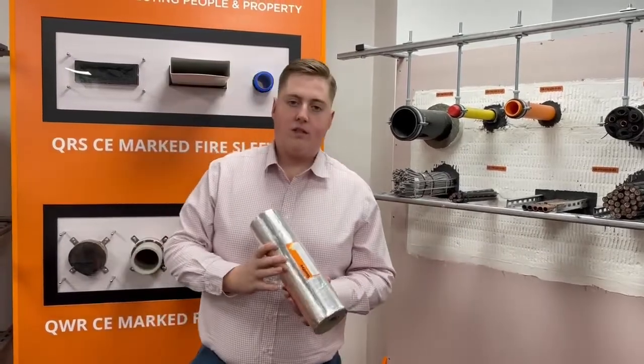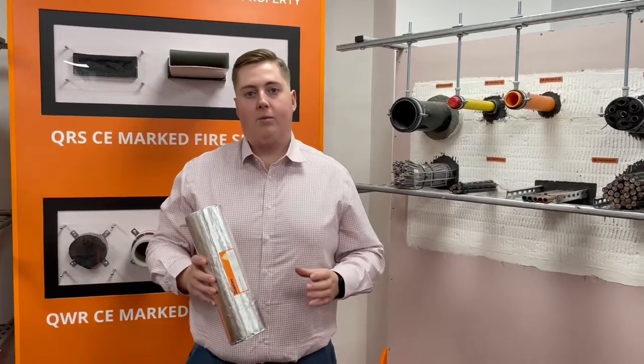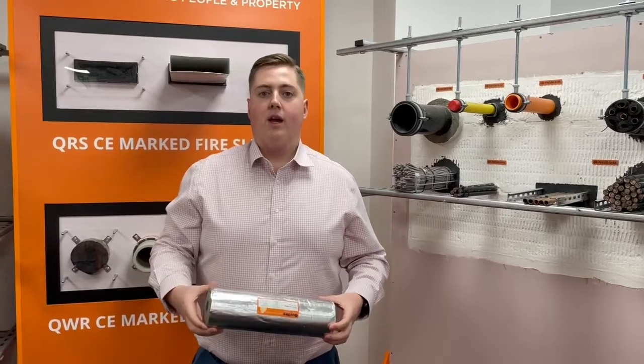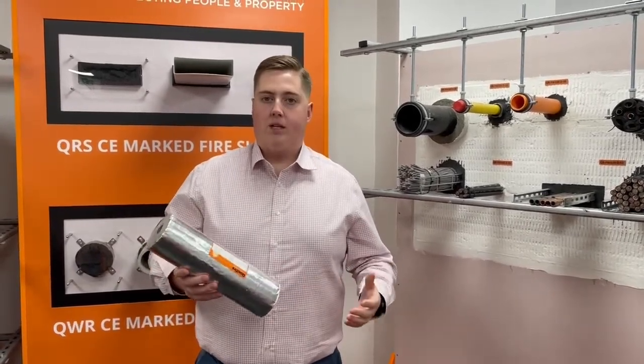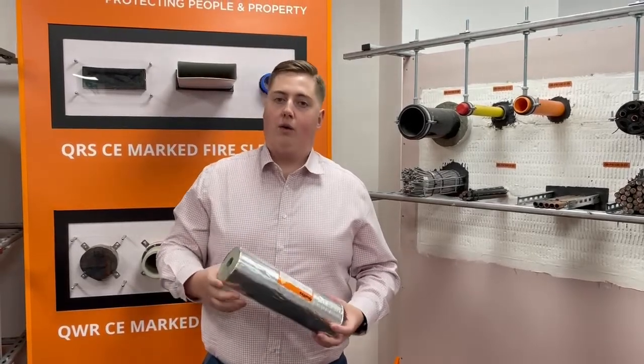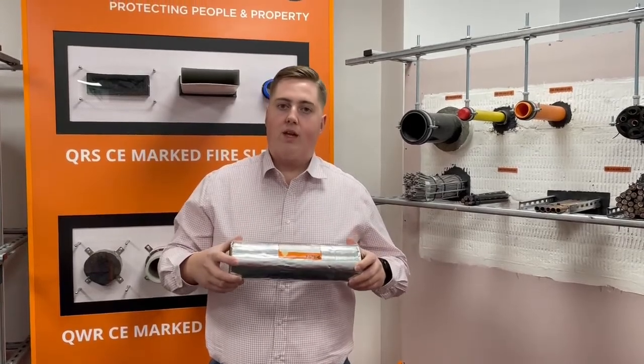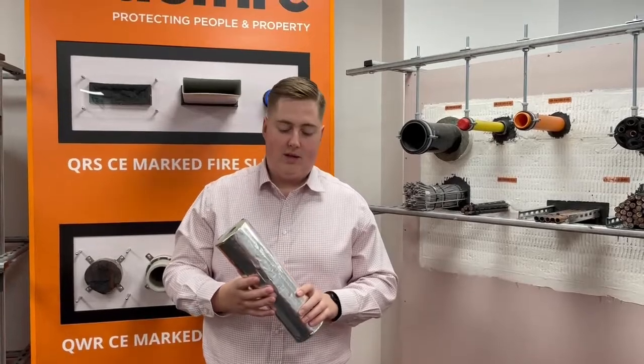In instances where you have insulated pipework in a building and that pipework penetrates a compartment wall, you can cut the insulation back that's on the pipework, install a QRS sleeve where it passes through the wall, and that pipe is then suitably fire stopped where it passes through the compartment. The sleeve also means that the pipe is still insulated, so you're not losing that element of the insulation.